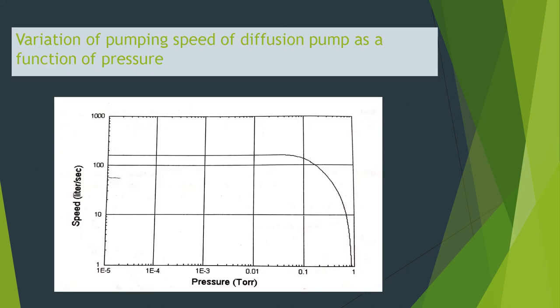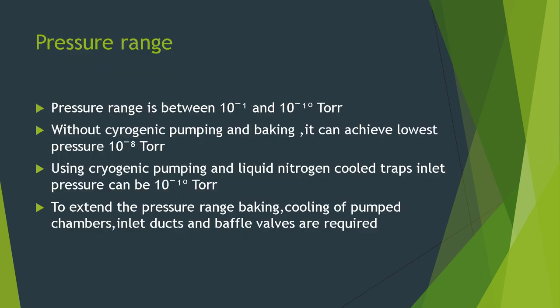This figure shows the variation of pumping speed of the diffusion pump as a function of pressure. When the pressure increases, pumping speed decreases after a particular limit. The operating pressure range is from 10⁻¹ to 10⁻¹⁰ Torr.